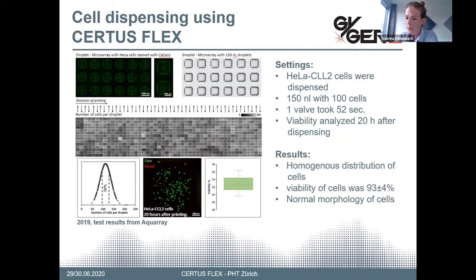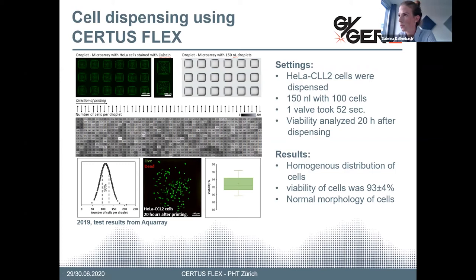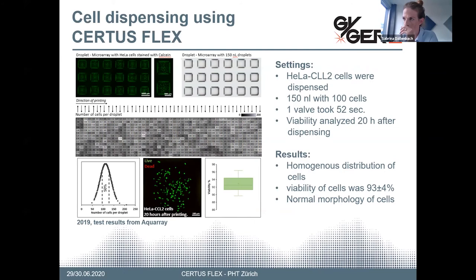For the DMA application, AquaRay used the CERTUS FLEX for dispensing HeLa cells, which you can see here stained with calcein. 100 cells were dispensed in a total volume of 150 nanoliters. The dispensing was performed in an S-line pattern, and using only a single valve it took 52 seconds in total to dispense a microarray with 672 spots. The viability of the cells was analyzed 20 hours after dispensing, and the results show: first, the cells were distributed homogeneously; second, viability was about 93 percent; and third, the morphology of the cells was comparable to those of a normal culture.